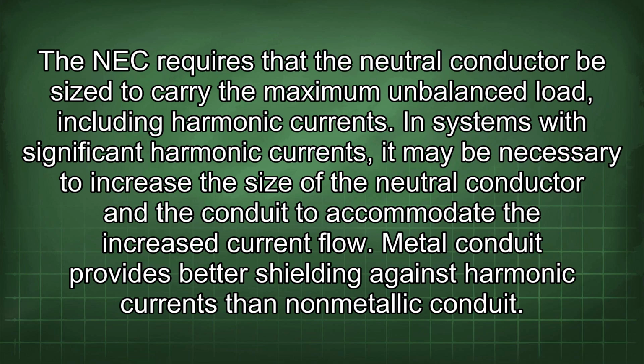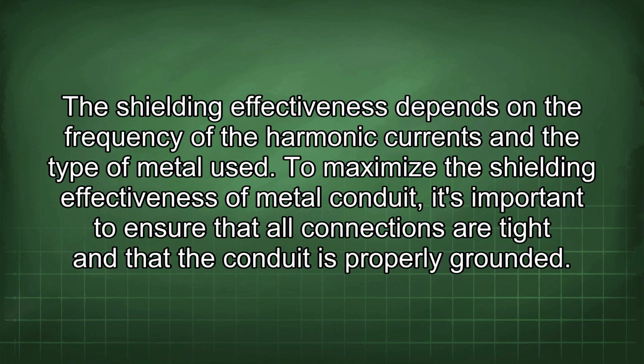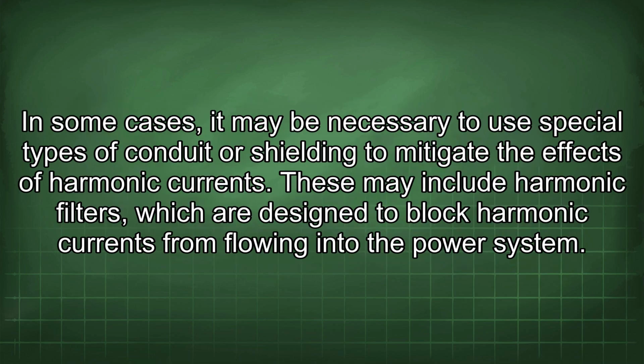Metal conduit provides better shielding against harmonic currents than non-metallic conduit. The shielding effectiveness depends on the frequency of the harmonic currents and the type of metal used. To maximize the shielding effectiveness of metal conduit, it's important to ensure that all connections are tight and that the conduit is properly grounded. In some cases, it may be necessary to use special types of conduit or shielding to mitigate the effects of harmonic currents.